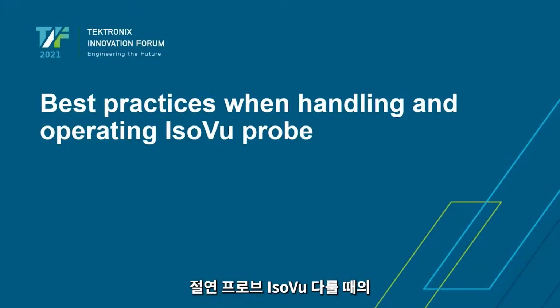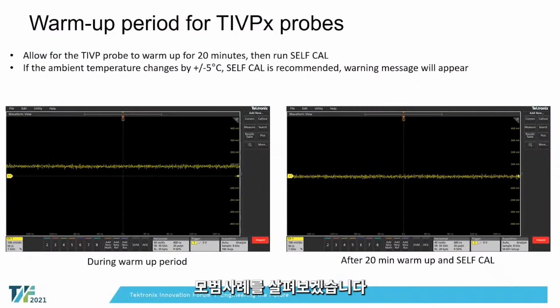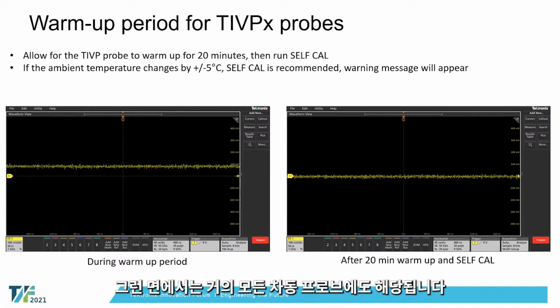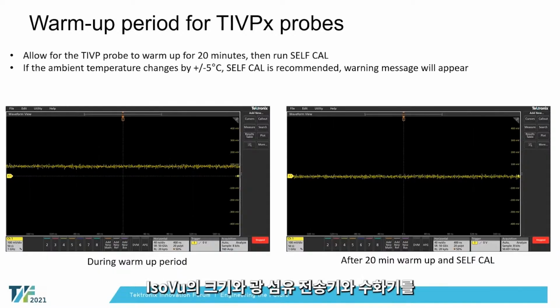All right, now let's get into some of the best practices when handling our isolated probe, IsoVu. One thing to keep in mind, and this is apparent with all active differential probes, is that there is a warm-up period recommended for any differential probe family. That allows the different components within the system of that probe to warm up and get to a steady state. That's true of an oscilloscope. That's true of most modern active differential probes, and IsoVu is no different in that regard. Because of the size of IsoVu and the complexity in using fiber optic transmitters and receivers, there is a slightly longer temperature warm-up period of 20 minutes that we recommend in our user manual. So be sure to keep that in mind when you're using IsoVu. It does take a little bit of time to warm up.